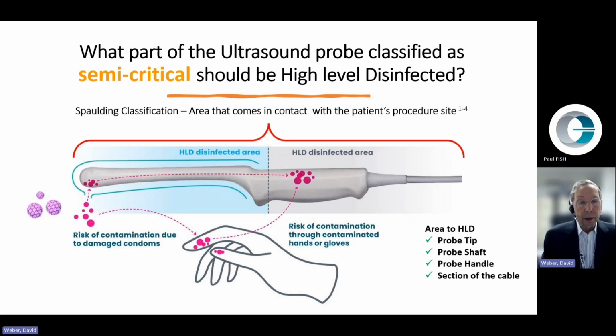On the right, where the probe handle is that you're touching and which joins the cables, there is a risk of contamination through contaminated hands or gloves if you touch either the mucous membrane of the patient or the probe that's inserted itself. So the areas for high-level disinfection include the probe tip, the probe shaft, the probe handle, and the section of cable that might be contacted by the gloved hands.